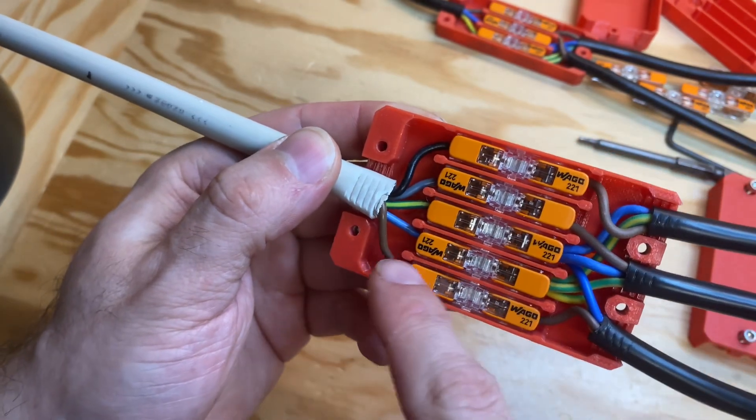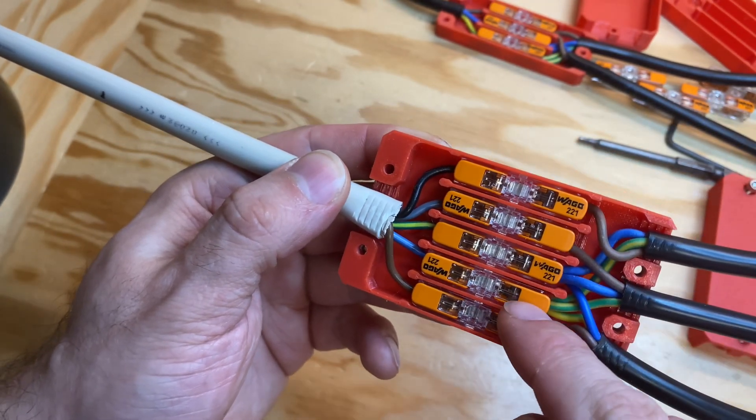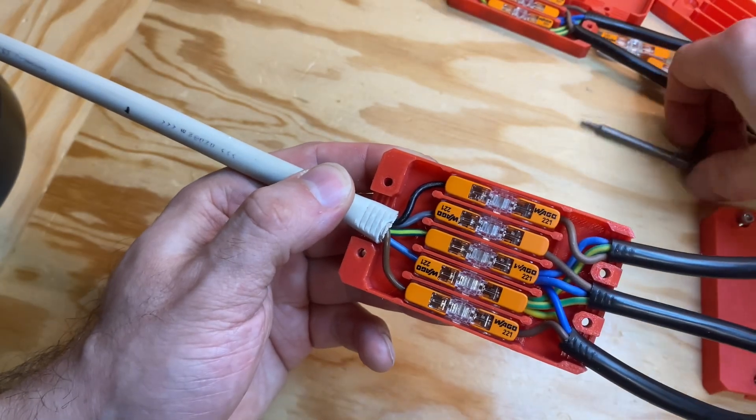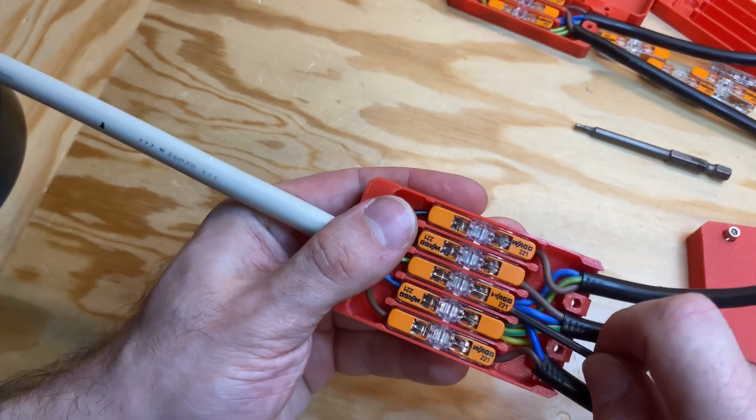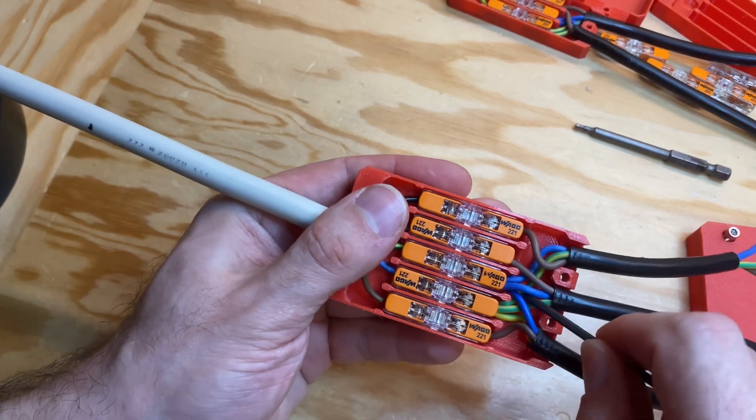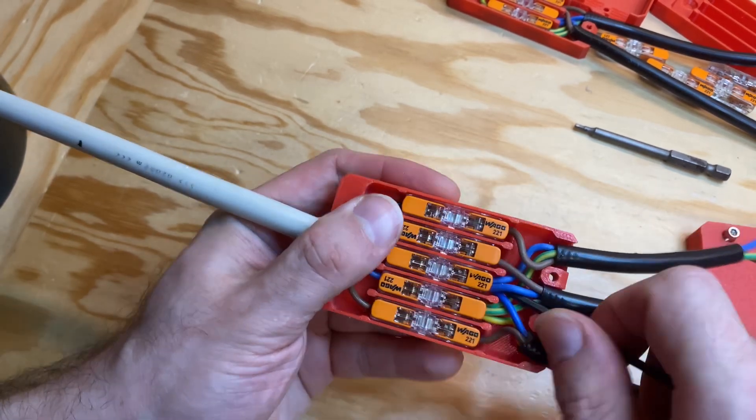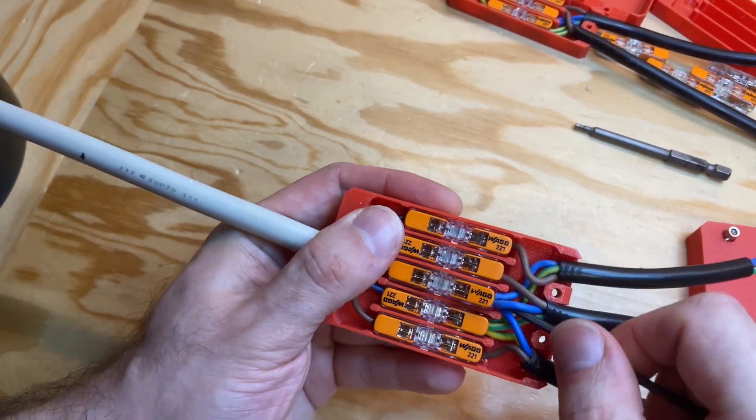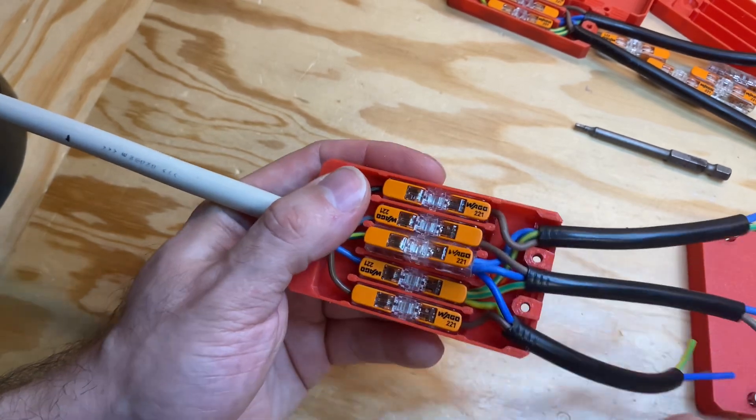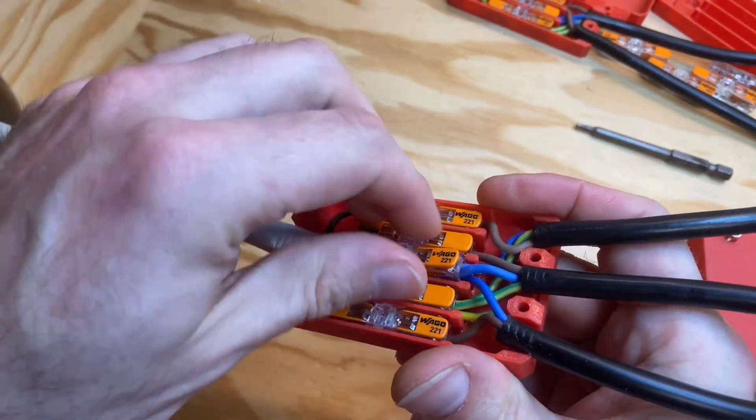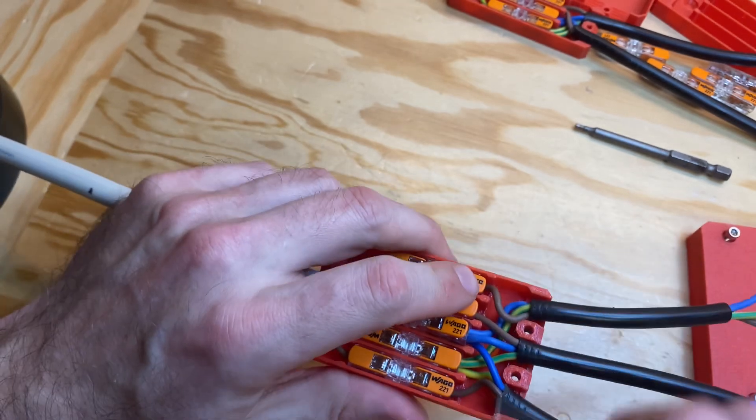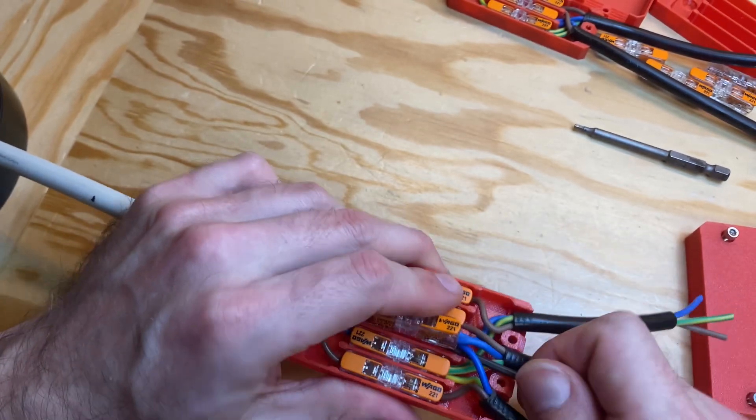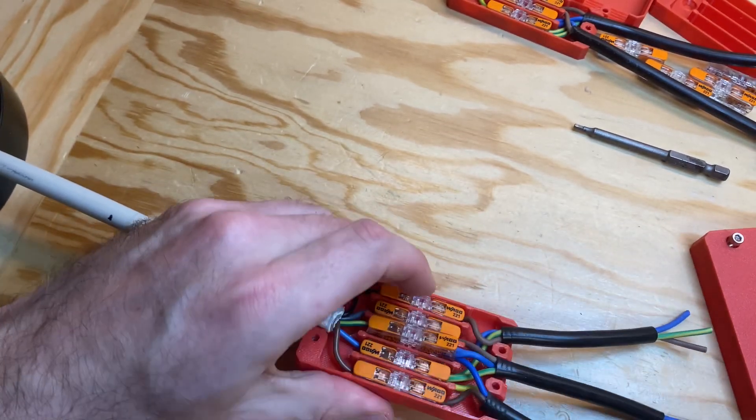So of course, what you have here is that the neutral and ground is shared between the three phases. And it's actually very important that this connection does not break, because otherwise you have a floating neutral, which burns electrical systems, burns down houses and such. So it's something that's really important to make a proper connection for.